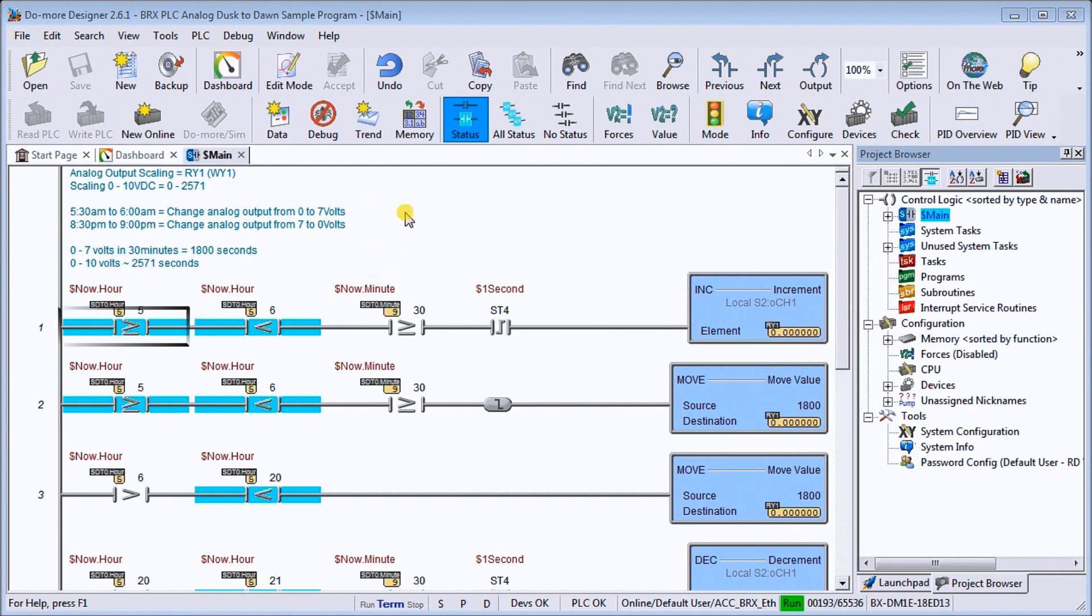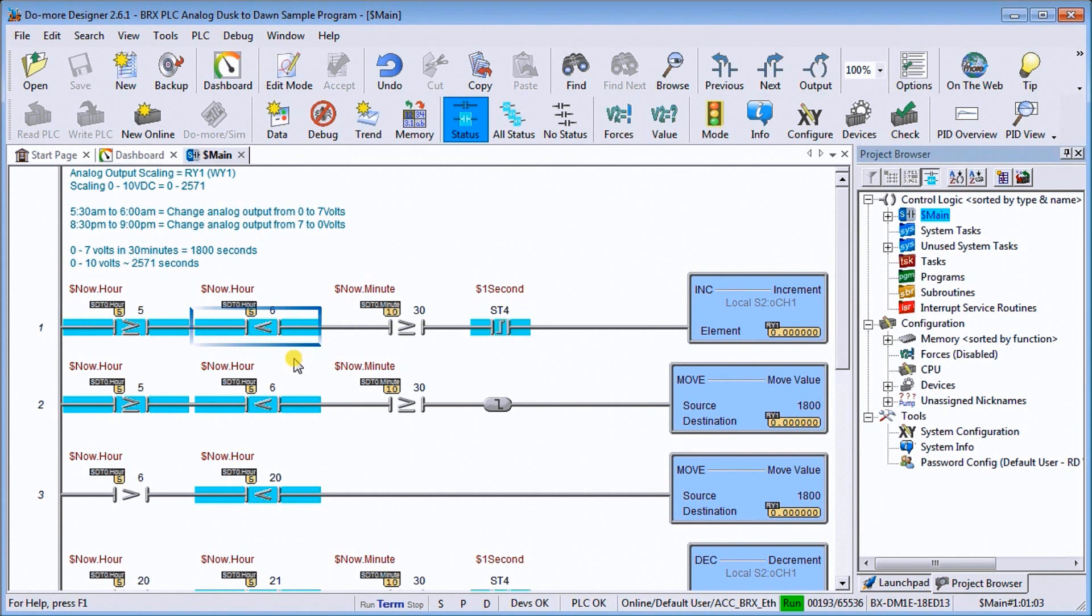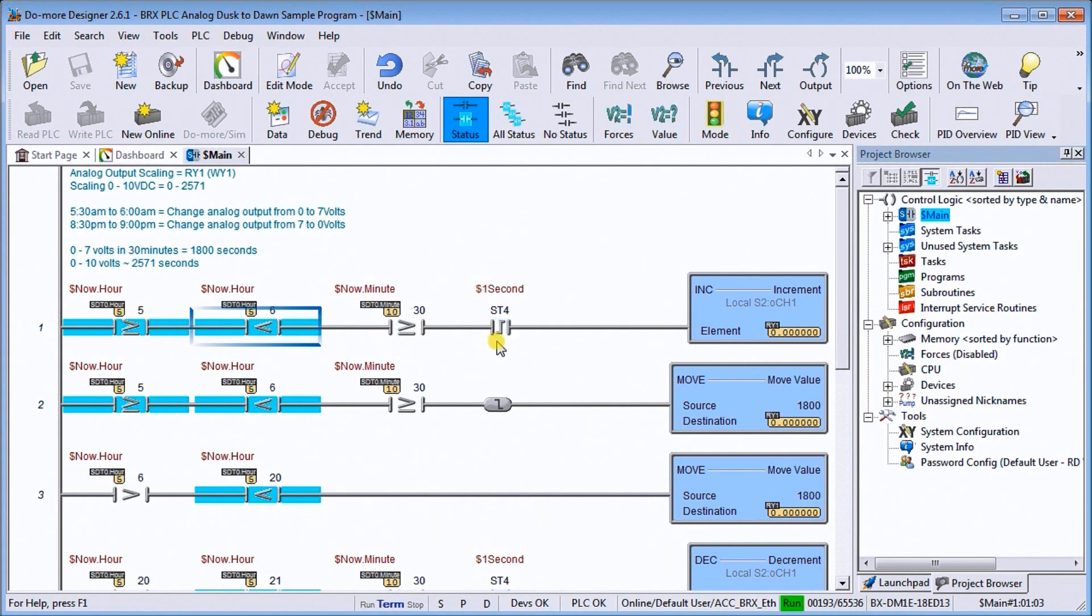So currently right now, you'll see my program. If I'm above or equal to the hour of 5 a.m. and I'm less than 6 a.m. or 6 in the morning, and I'm greater than 30 minutes, then I start a one second pulse on a leading edge, which then will increment my scaled RY1 value.